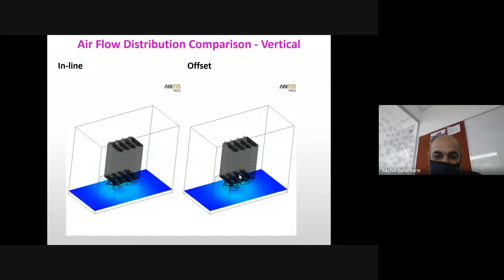So here what I have done is I have taken three planes, bottom, middle and top. Top line is inline and bottom is offset. So by offsetting the fans, there is a large area which is covered by the air for the heat dissipation, and it improves the heat dissipation. Now here in inline configuration, this is the area of the radiator which gets wasted. That means the air is not reaching these areas, and there is a reduction in the heat dissipation due to loss of areas which are not utilized fully for the heat dissipation.